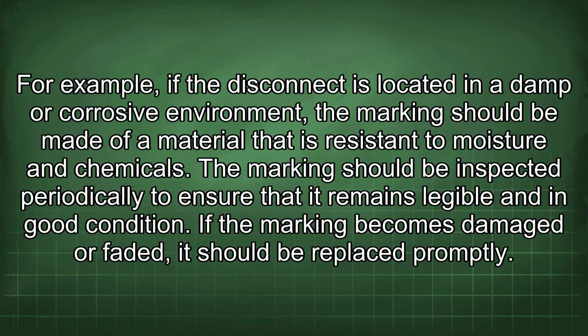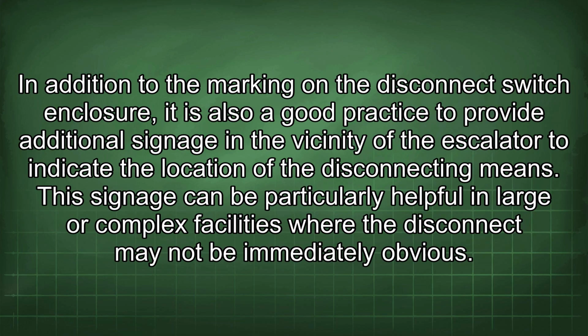The marking should be inspected periodically to ensure that it remains legible and in good condition. If the marking becomes damaged or faded, it should be replaced promptly. In addition to the marking on the disconnect switch enclosure, it is also a good practice to provide additional signage in the vicinity of the escalator to indicate the location of the disconnecting means. This signage can be particularly helpful in large or complex facilities where the disconnect may not be immediately obvious.